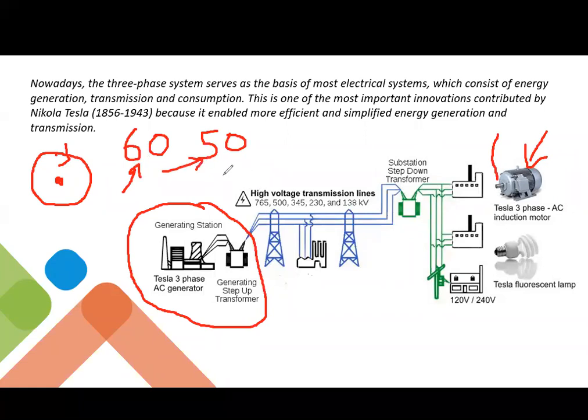But with the three phases, we could definitely provide electricity to a variety of customers. And during that time, we wanted to transmit this as long a distance as possible. It would be nice to be able to go from Niagara Falls all the way to Miami. To do that, we definitely had to increase the pressure. Sometimes we would get these transmission lines, you can see up to 138,000 volts, just so that we had enough pressure to push that electricity to wherever we wanted it, to eventually our industrial customers and even our residential customers.